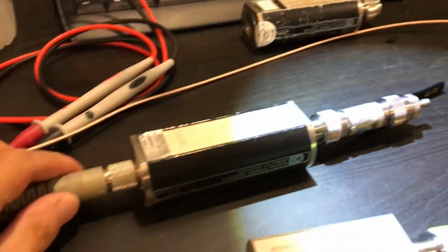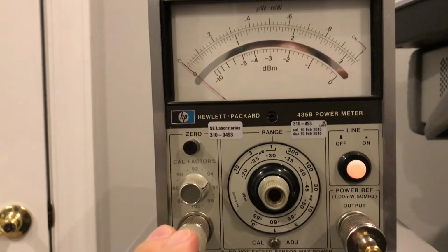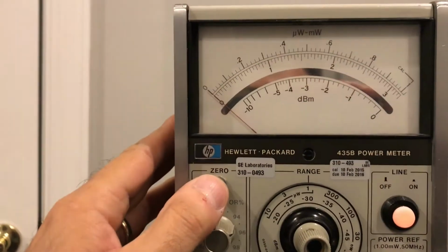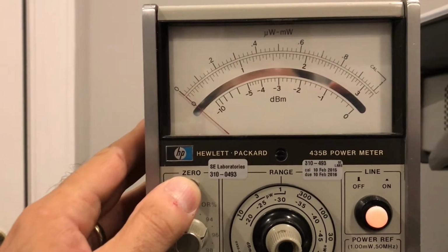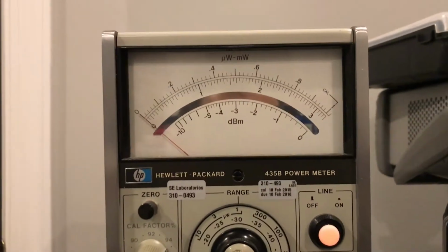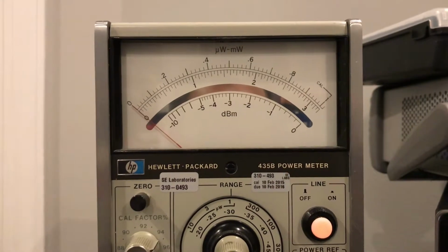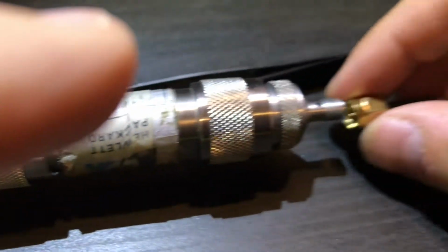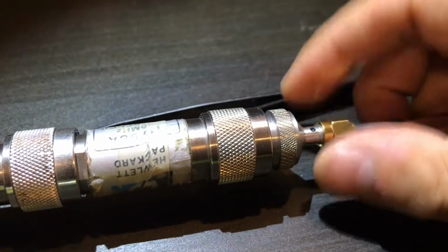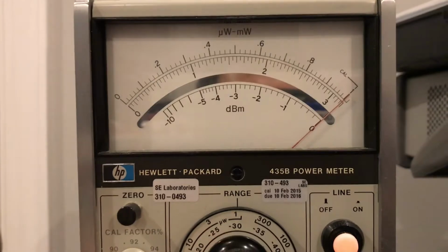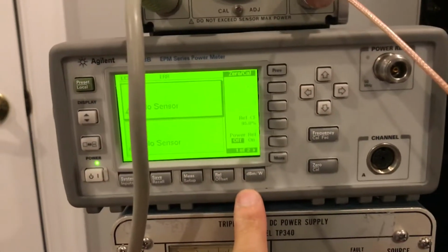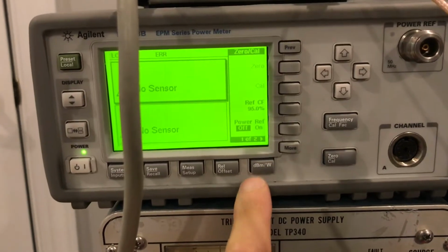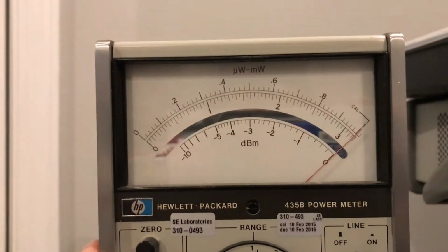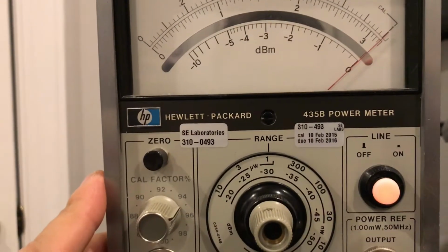Alright, so we've got the unit hooked up now to the 435B, and we hit the 0 button, and we can see that the power sensor appears to be zeroed at this point. So what I'm going to do now is we'll attach the reference signal. Alright, and unlike before with the Agilent 4418B power meter, on the 435 we can in fact cal the sensor.